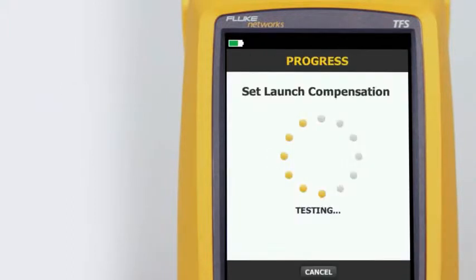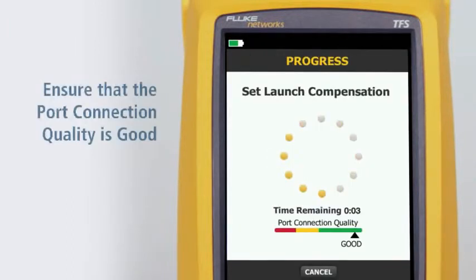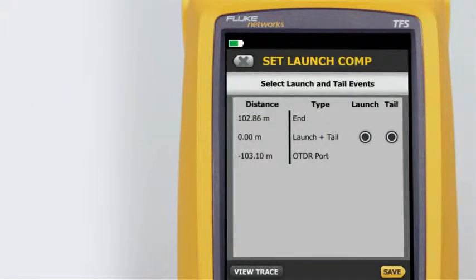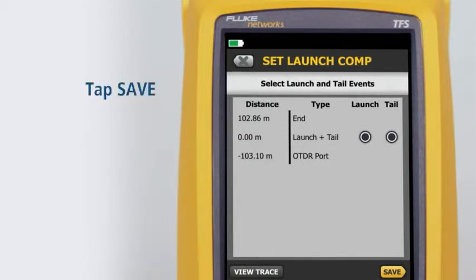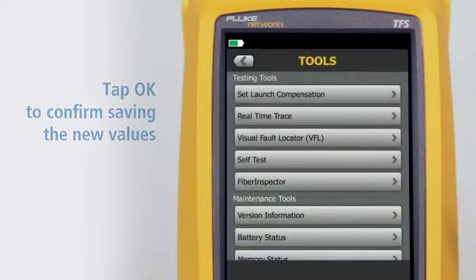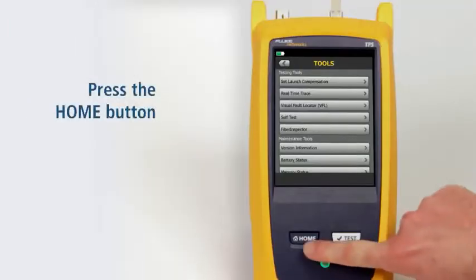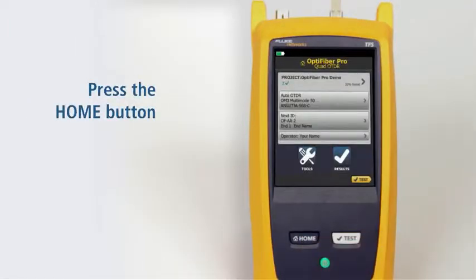The tester will analyze the launch and tail cord properties. Ensure that the port connection quality is good. The connection between the launch and tail cords is both the launch and tail event because we've connected the two cords together. Tap Save, then tap OK to confirm saving the new values. Press the home button — we're ready to run a test.